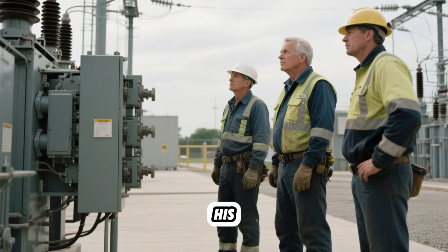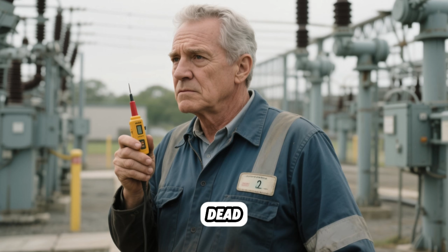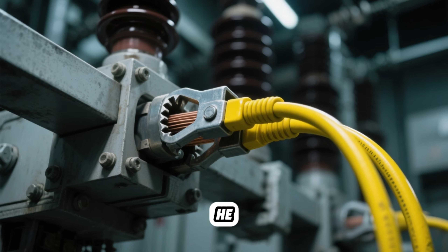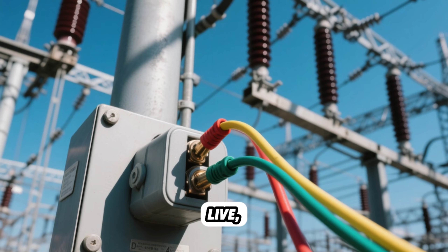The clearance, a guarantee that a piece of equipment is de-energized and locked out, had been issued. They tested for voltage and confirmed it was dead. But as the lead lineman approached, something felt wrong. He paused and looked around. He noticed a temporary jumper cable, installed by another crew weeks before for a different job, that was still in place. This jumper was backfeeding the de-energized switch from a completely different and very much live circuit.